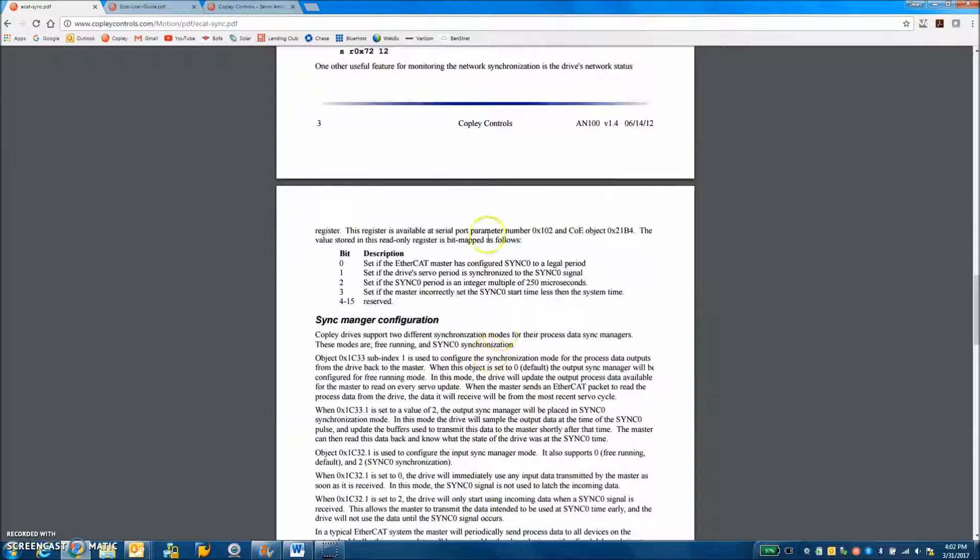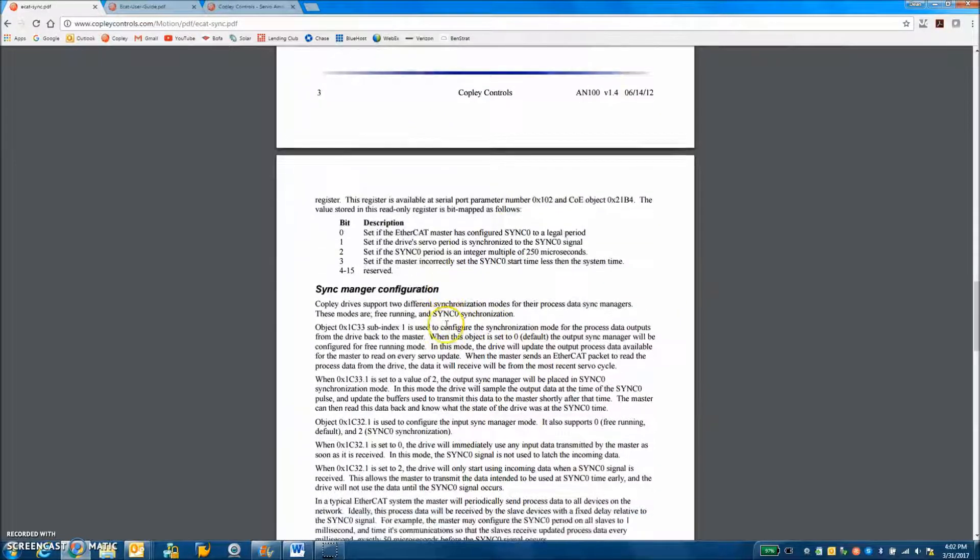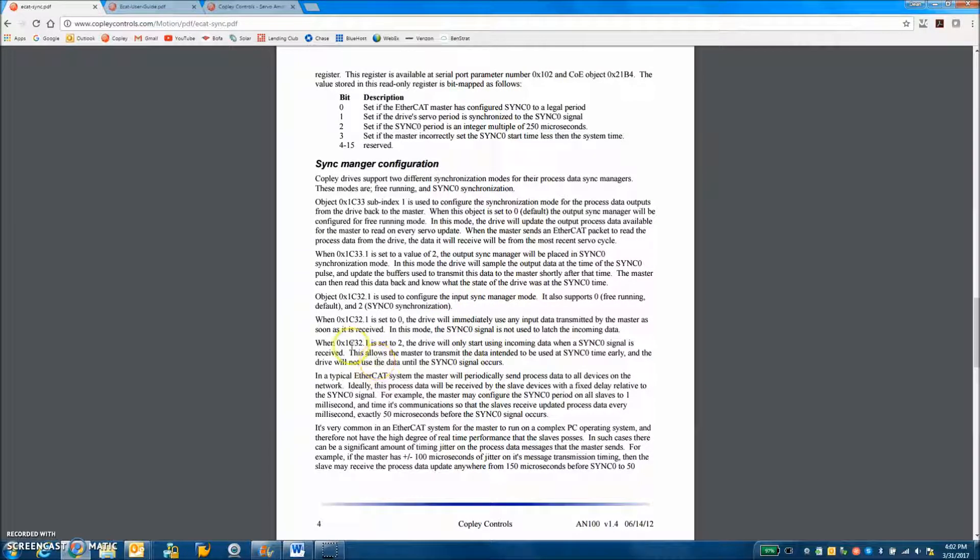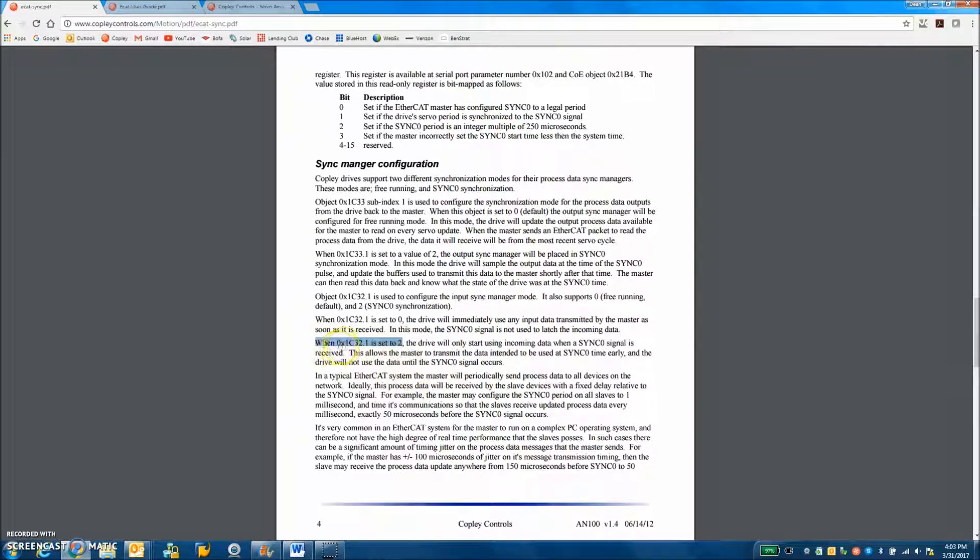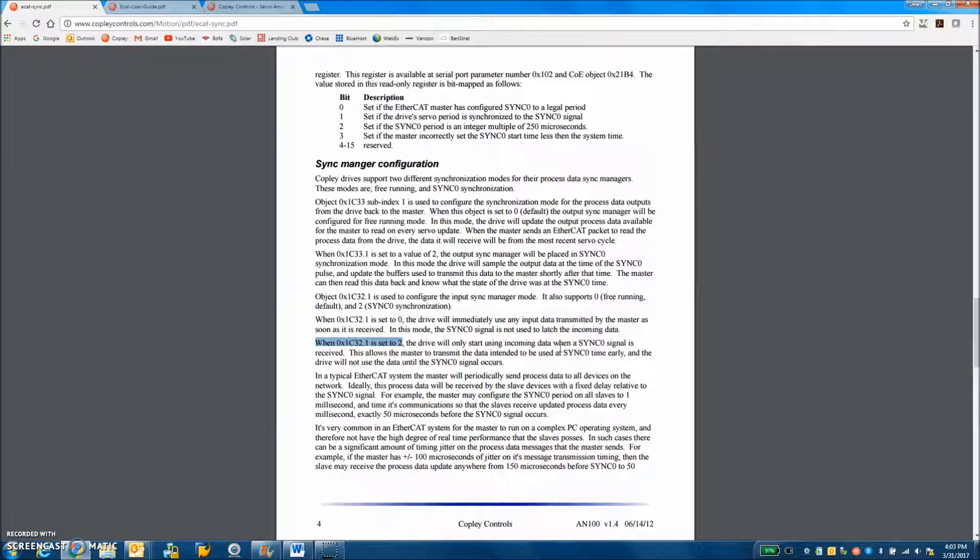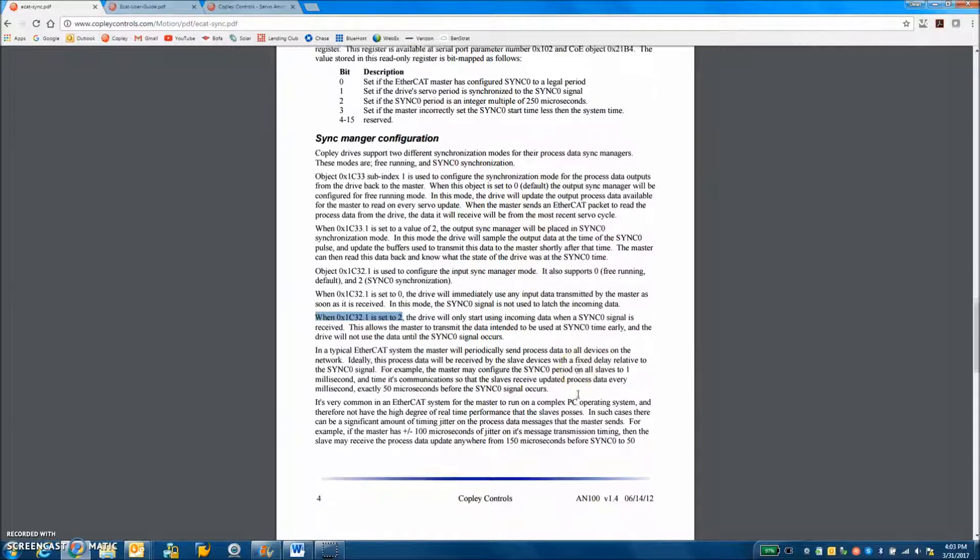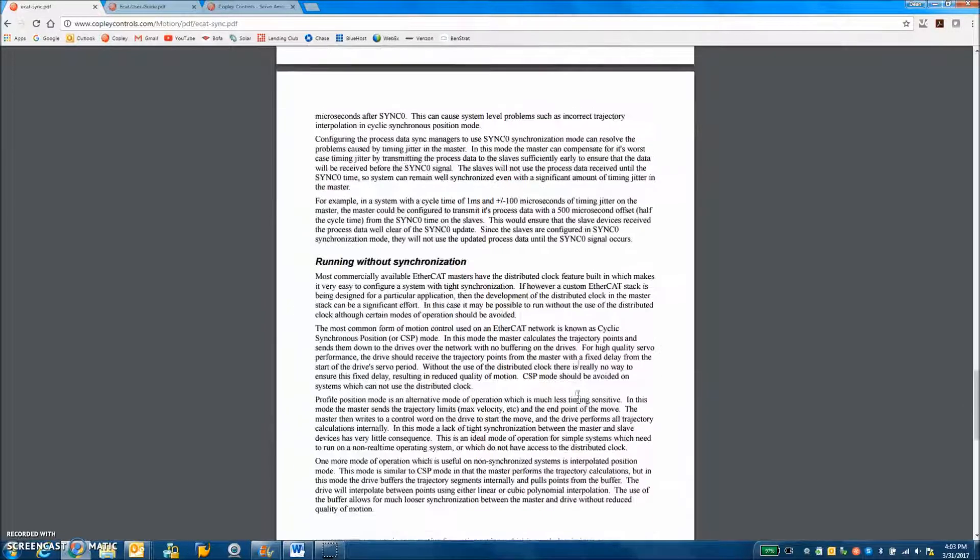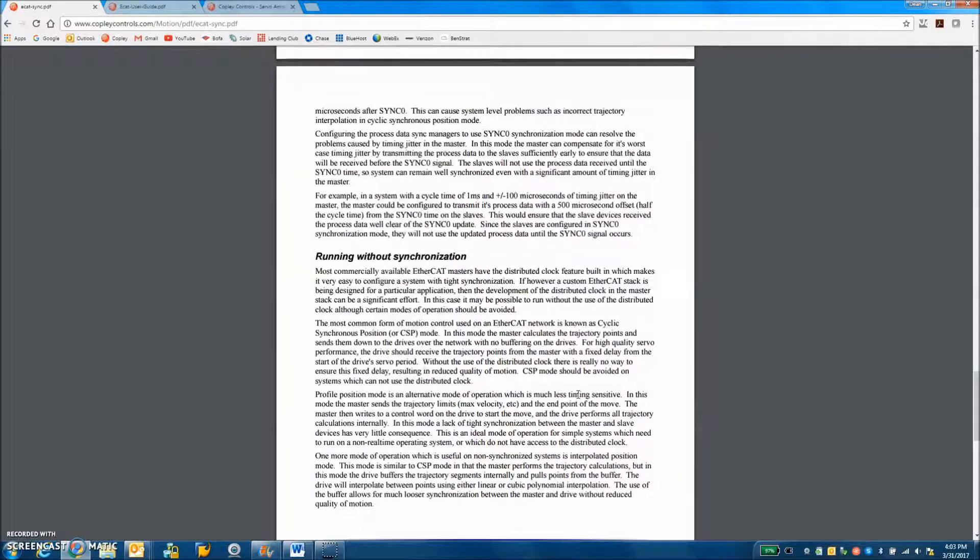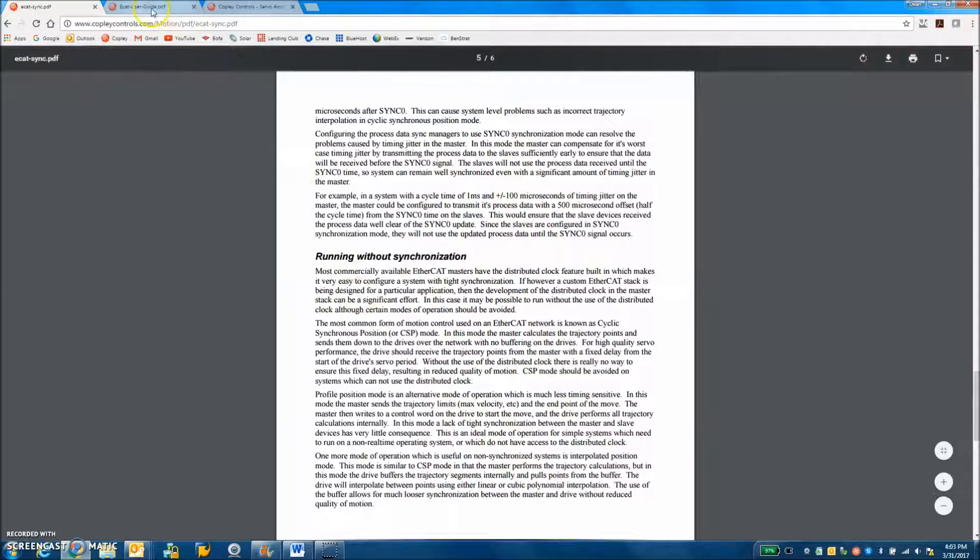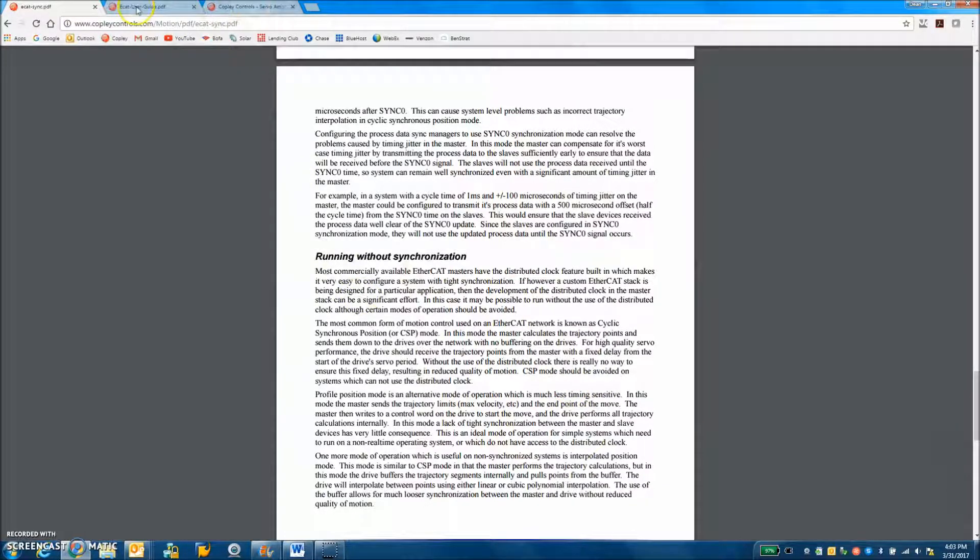This is the configuration of the serial interface using the ASCII command tool from CME2. So that's good debugging. Configuring of the sync manager. I like this one here, 1C32 subindex 1 set to 2. And you send the position command and it holds it until you get the sync zero pulse. So that's pretty cool. I'm not even going to read how to run without a synchronization because that doesn't make sense to me.